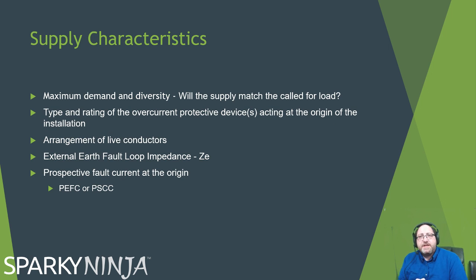Some of the things we need to consider. Supply characteristics. Have a good look either in Guidance Notes 3 or the wiring regulations themselves at the certification. Look at what the supply characteristics are and look at what we need to report. You'll be picked up on those, so that the assessment knows that you know exactly what you're looking for straight away.